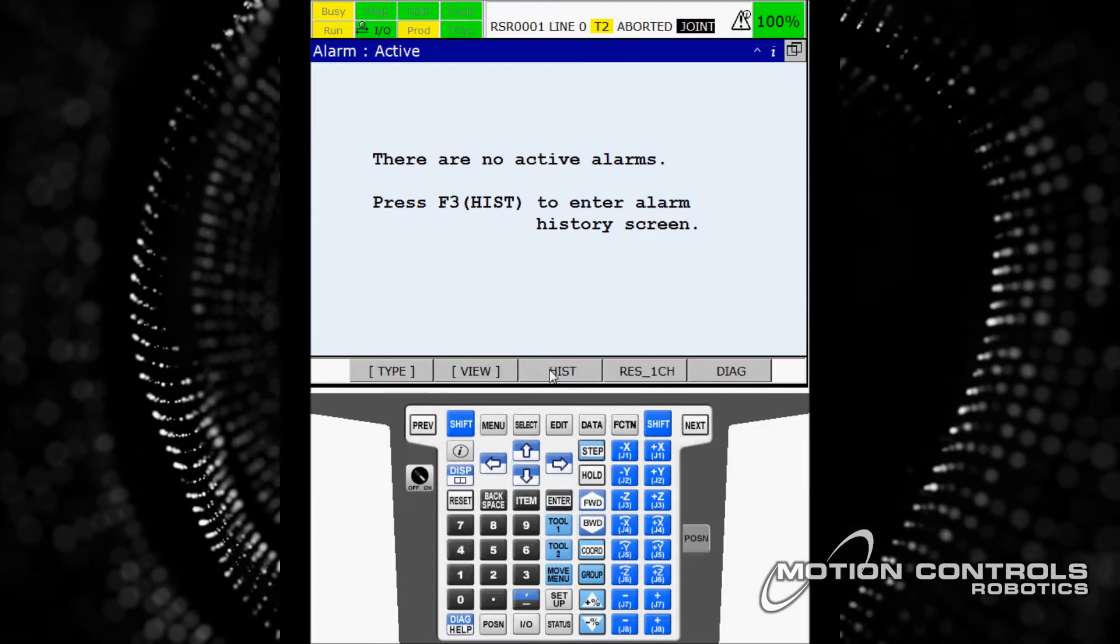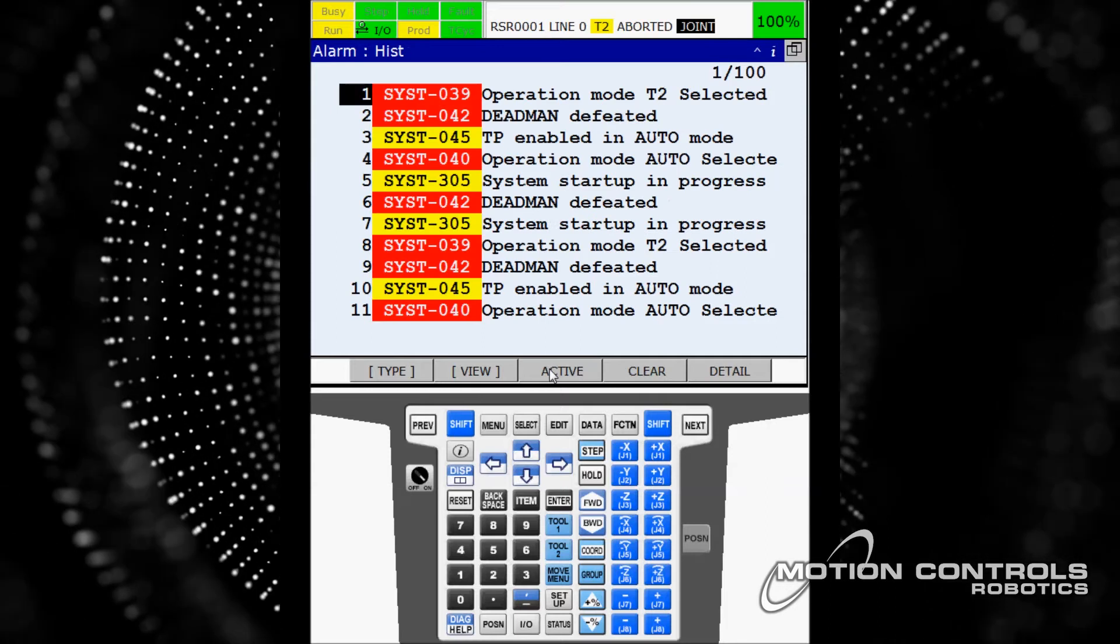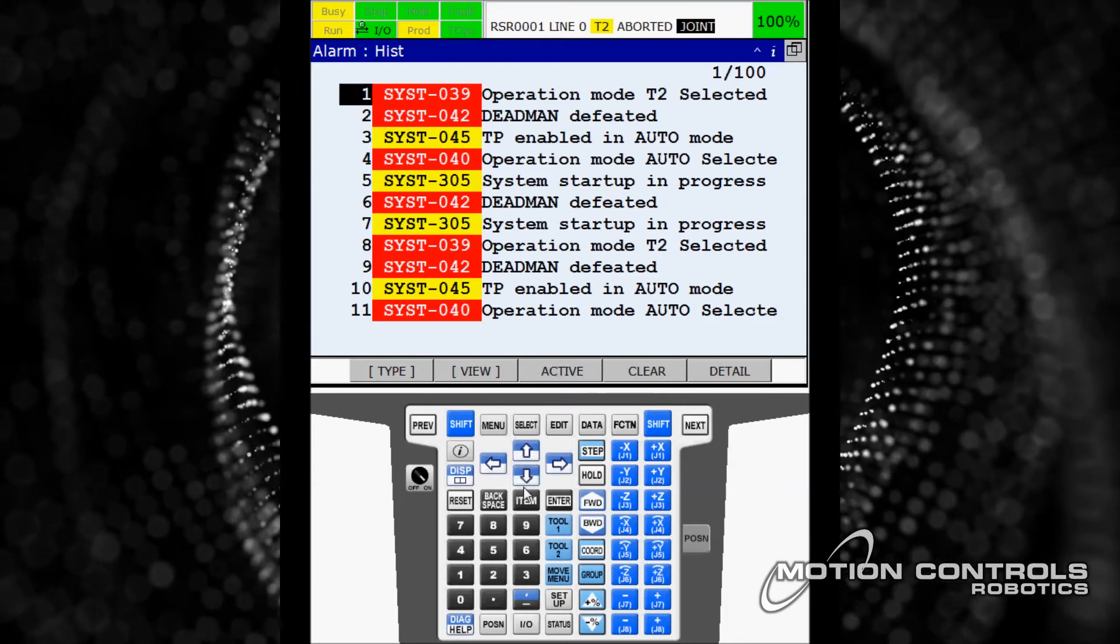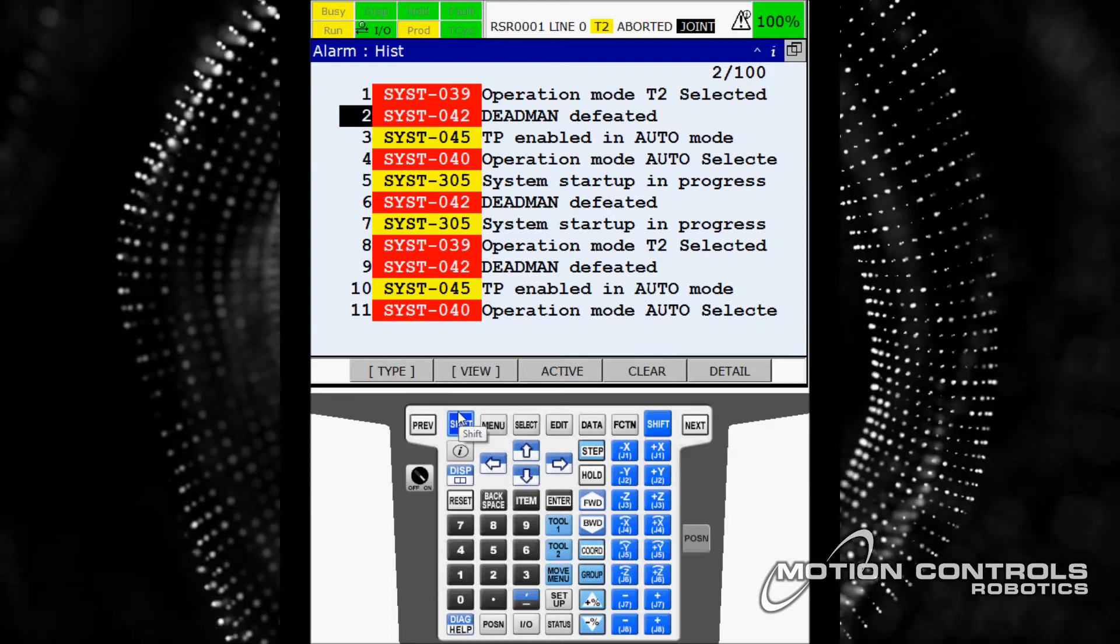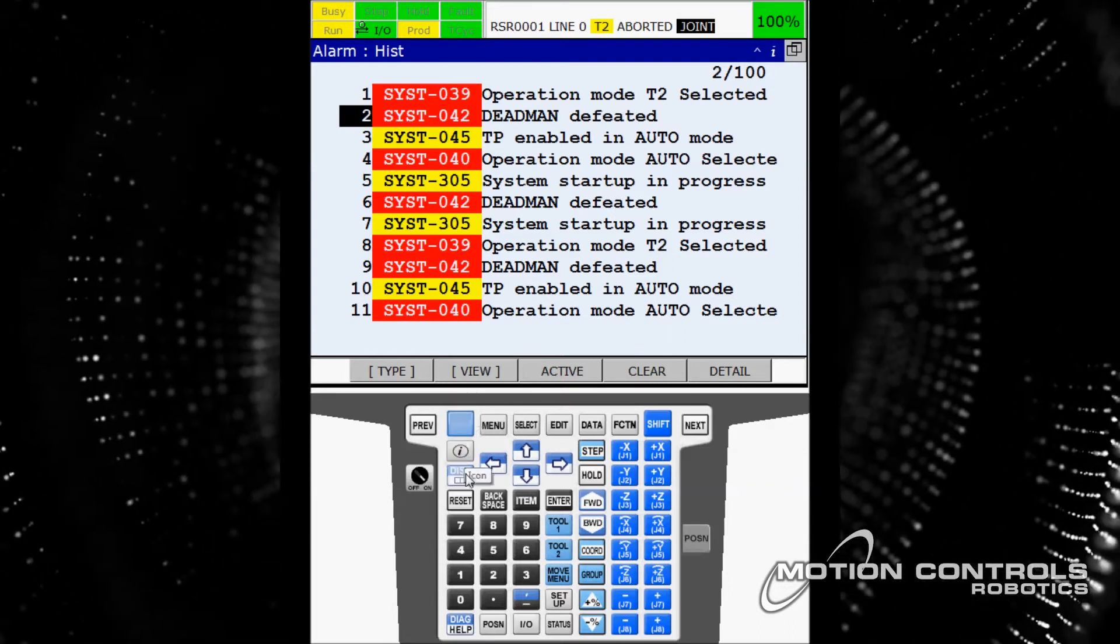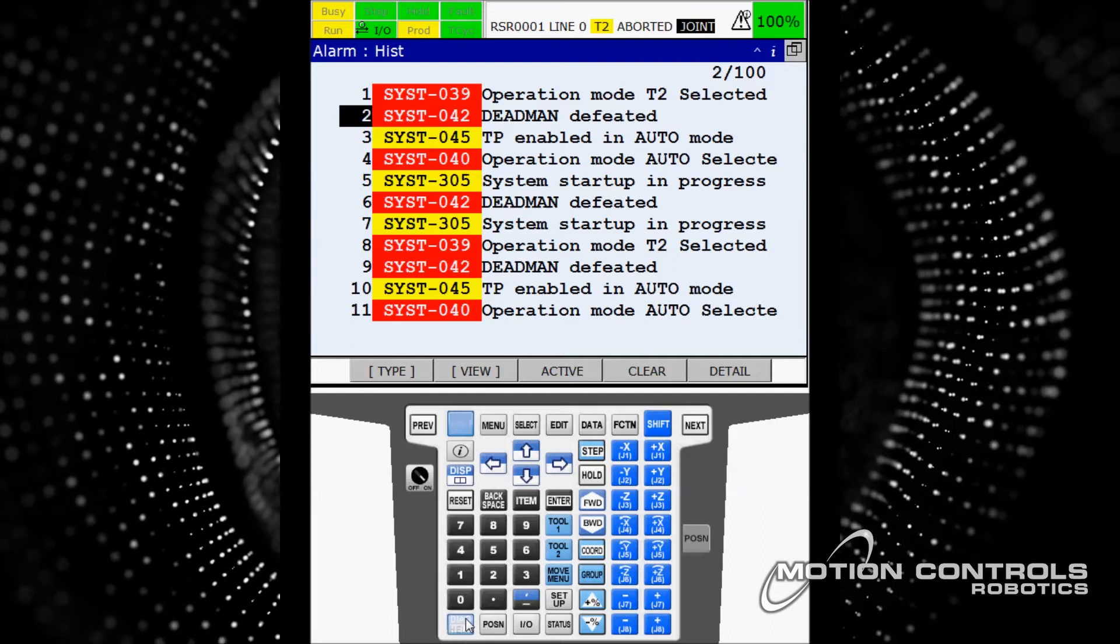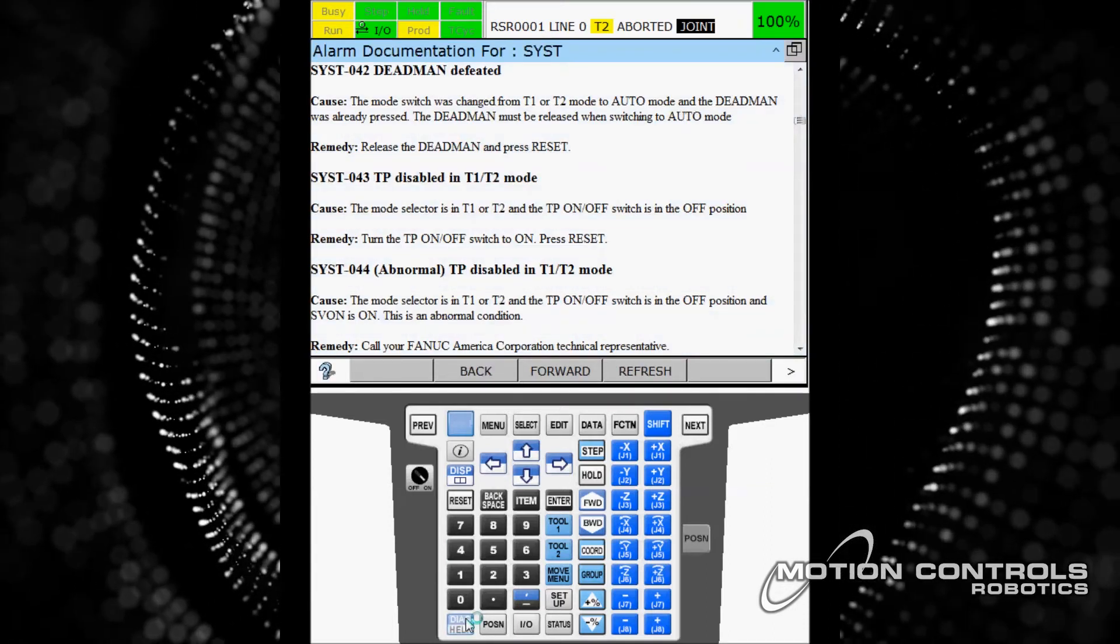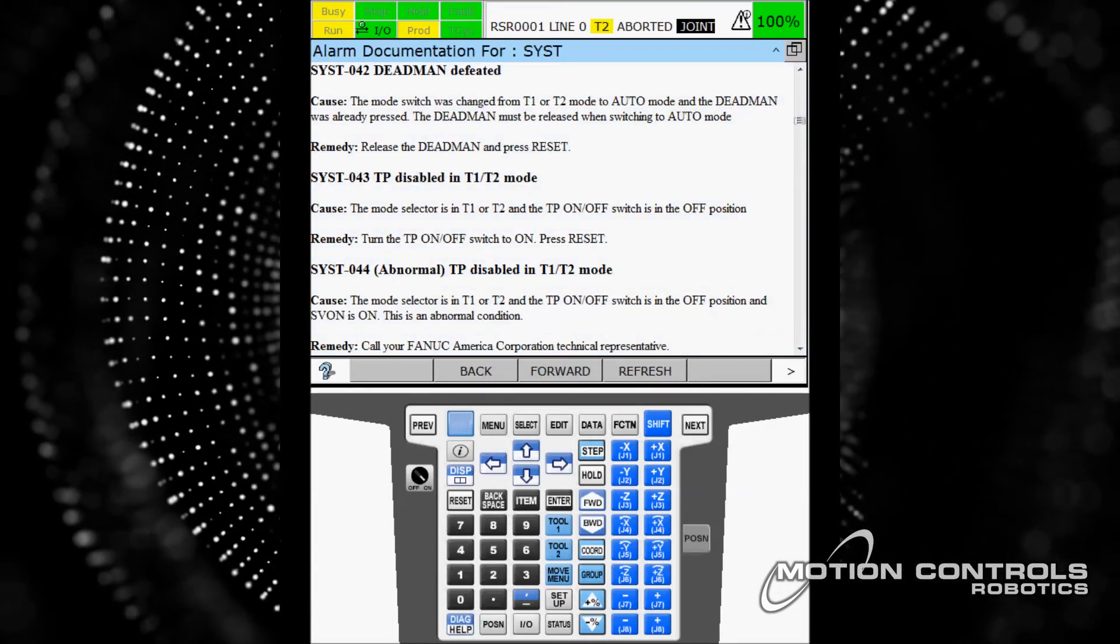To go to Alarm History, select History on the top-line menu. Scroll through the 100 alarms here using arrows. Highlight the errors or faults you want to learn more about. Press the Shift and Diagnosis Help button together for troubleshooting causes and remedies.